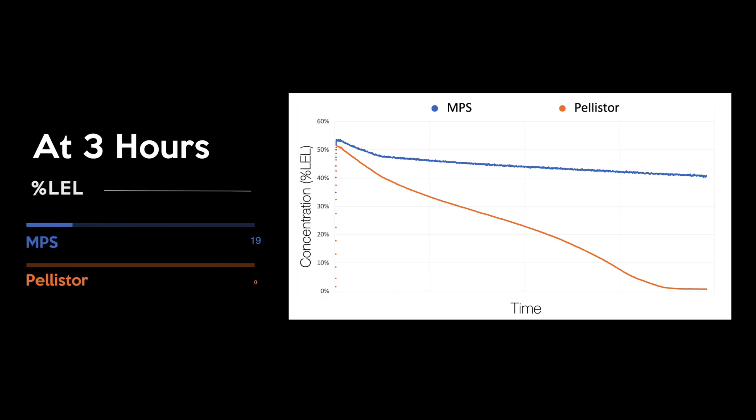At three hours, the pellistor reads 0% LEL while the MPS is reading 40% LEL.